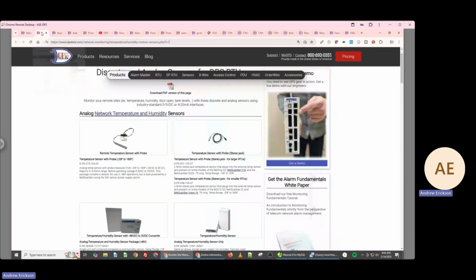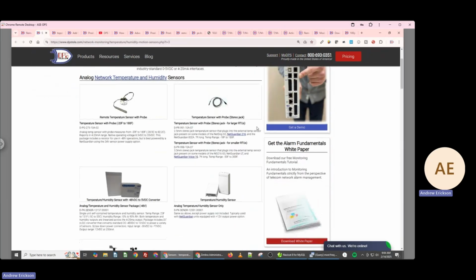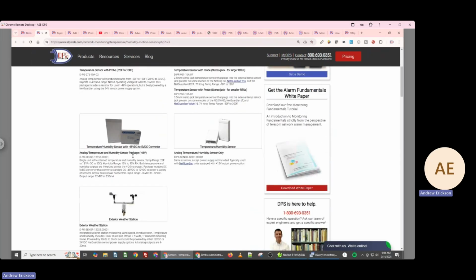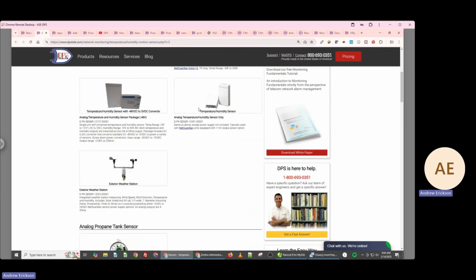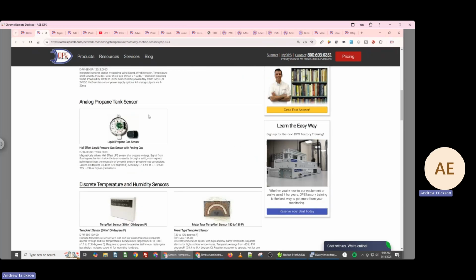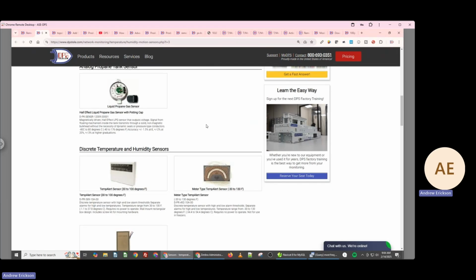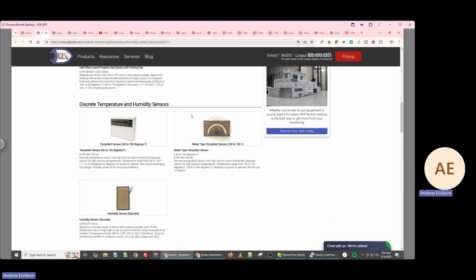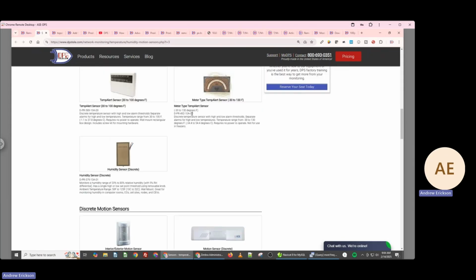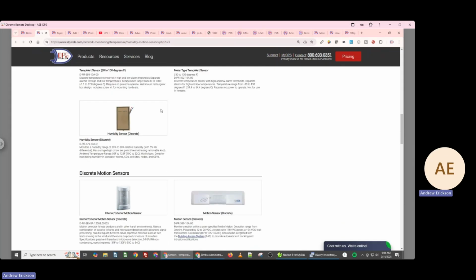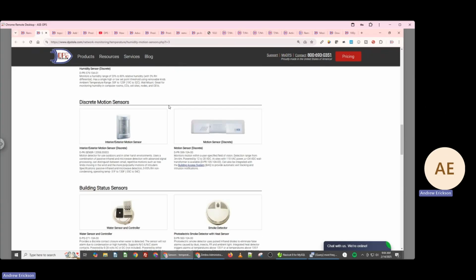If you look at our sensors page, these are mostly third-party sensors, though this one I think we built. You see all sorts of things you might want to monitor. Whenever I get a strange new request - hydrogen sniffing was a relatively new one in the last couple of years, for battery off-gassing. That's not a sensor we manufacture; it's something that either latches a contact closure or sends us an analog voltage or 4 to 20 milliamp current, which we can pick up at the NetGuardian.